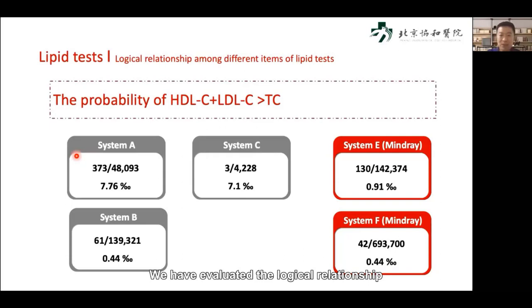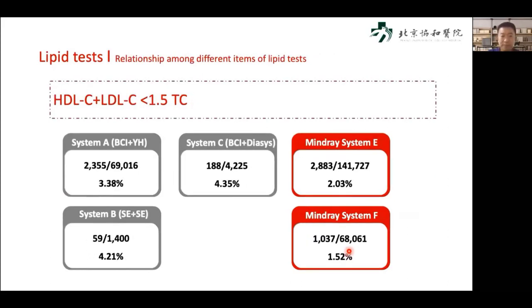We have evaluated the logical relationship between TC, HDL-C, and LDL-C using reagents from different manufacturers. The occurrence rate of HDL-C plus LDL-C more than TC using reagents from different manufacturers varied significantly. The highest rate was 7.8 thousandths. The lowest rate was 0.44 thousandths. The occurrence rate using Mindray reagents was below 1 thousandth. In addition, when HDL-C plus LDL-C are much smaller than TC, we need to consider the accuracy of LDL-C and the distribution of cholesterol in different lipoproteins.